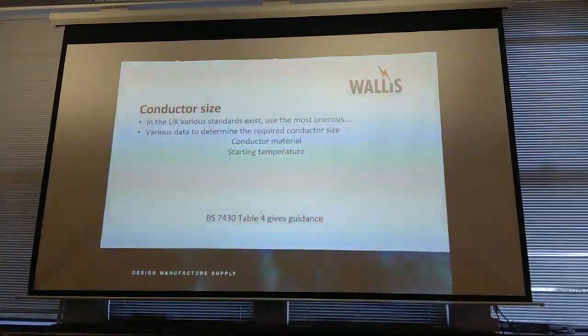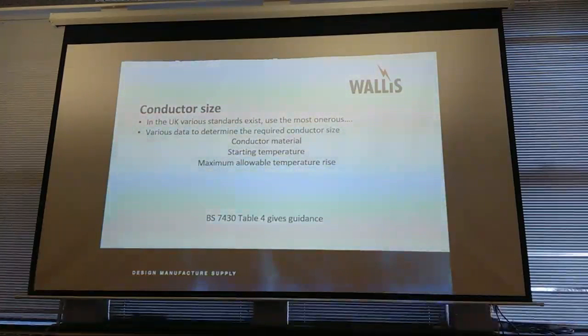Starting temperature, you need to know the starting temperature. We tend to work to 30 degrees C. Again, worst case, UK summer, sitting in a switch room or something like that, we would hope it's going to be about 30 degrees C. Maximum allowable temperature can vary. I think 7430 talks about 250 degrees C, and that is where it's passing through concealed or confined areas, such as through wall spaces or somewhere like that. You've then got ENA TS 41-24, which talks about a maximum temperature of 400 degrees C, and that's for copper in the ground in an open gear substation.